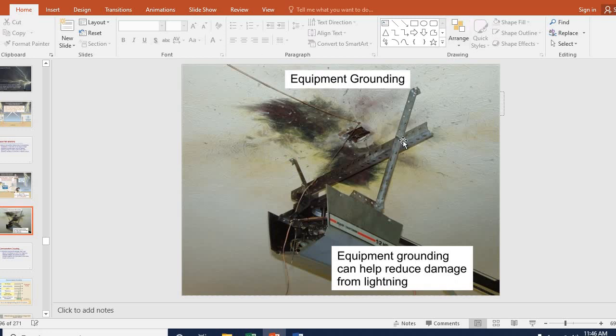I've actually seen stuff like this happen. I've seen it blow out every receptacle in a room. And I've also seen it blow off a 200 amp panel cover. The lightning struck the corner of the house on a 2-story house, and the 200 amp panel was in the carport at the opposite end of the house, and it caused a lot of damage. We worked a lot replacing bad stuff that it jumped on, and it was grounded properly. You can't stop all of it.